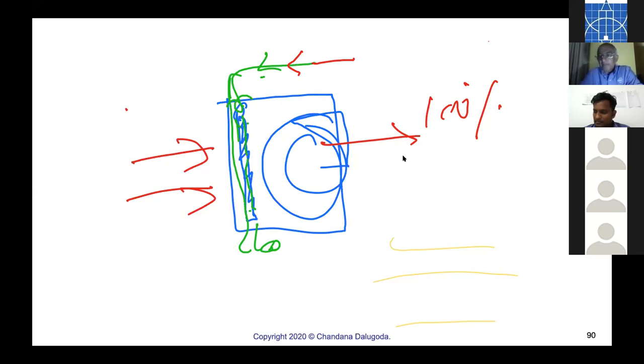Just a second, sir. Very correct. Further lowering the chilled water supply side, though we are getting the saving from the pump side, we are compromising the chiller lift. Then your chiller consumption may be offset by the saving that we are getting. Regarding the 14 degrees, since you have gone through the latest 90.1, they are saying the return should be minimum 40. That means they are asking us to go a little higher if possible. Of course, there can be restrictions.